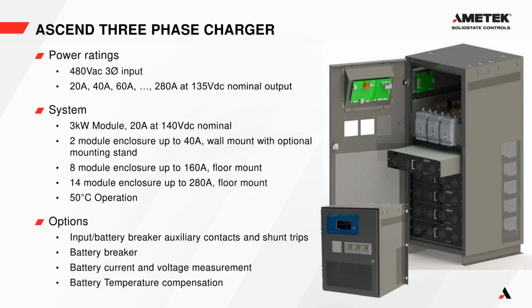This will allow you to have a separate breaker, and you can also have the option for monitoring for the battery voltage and current. If you choose this option, the battery current and voltage metering option, when the AC input is lost, the battery will continue to supply the power to the display board inside of our system, and it'll also allow you to see the discharge current of the battery and the voltage.